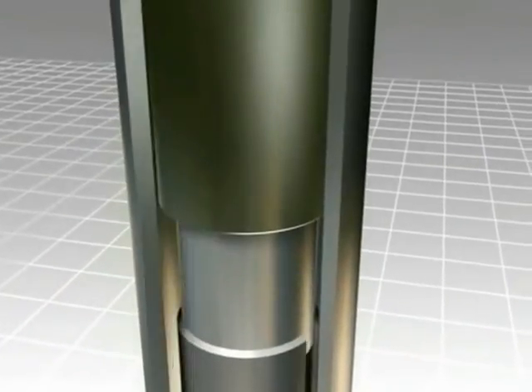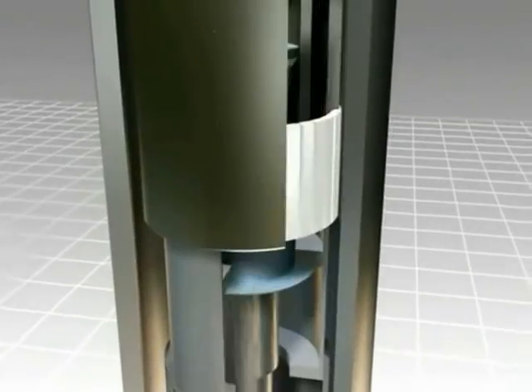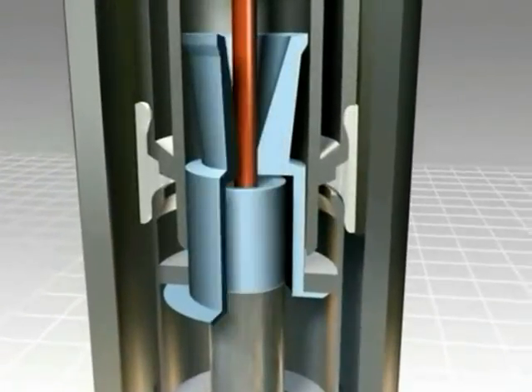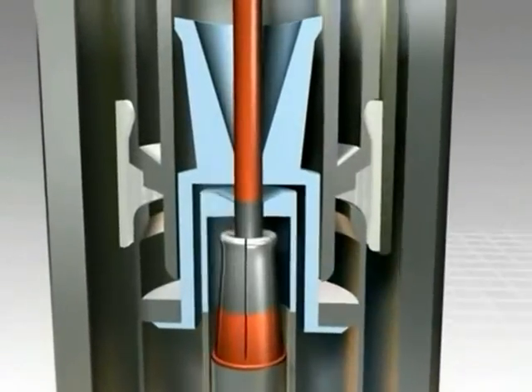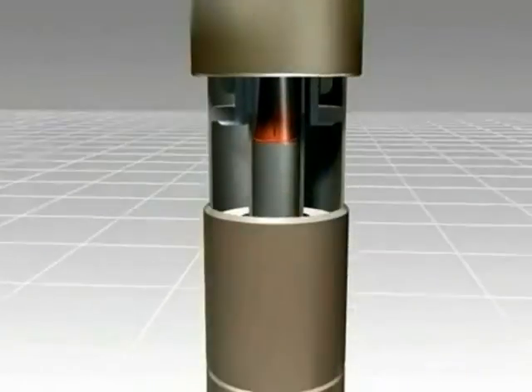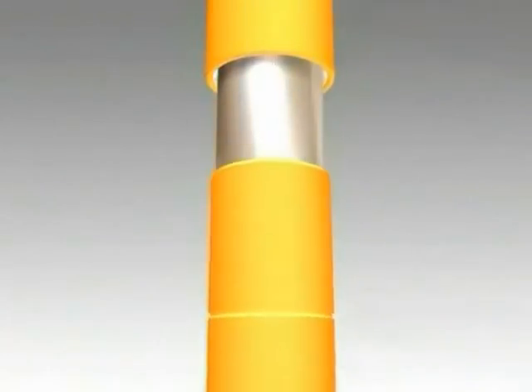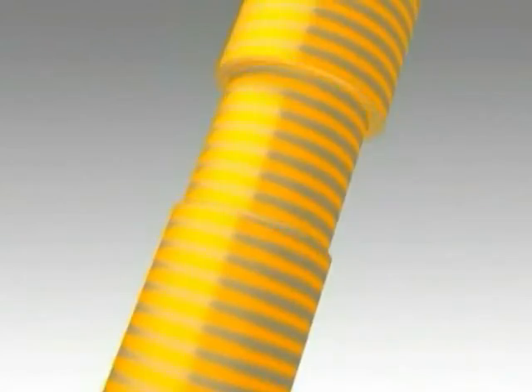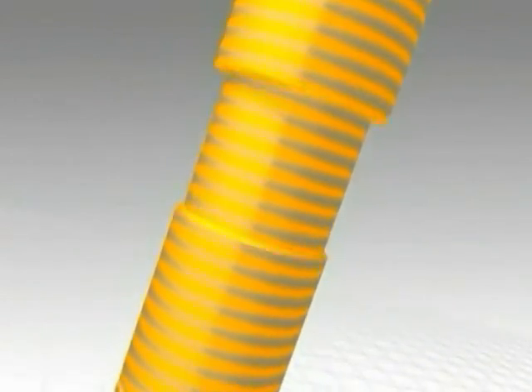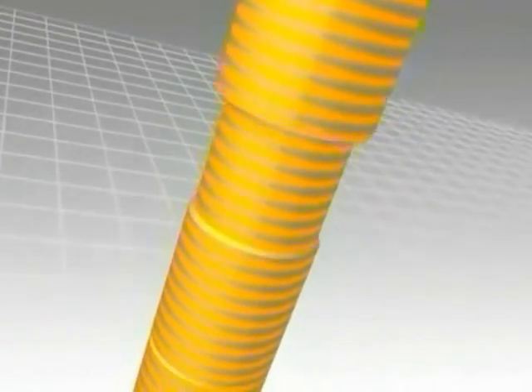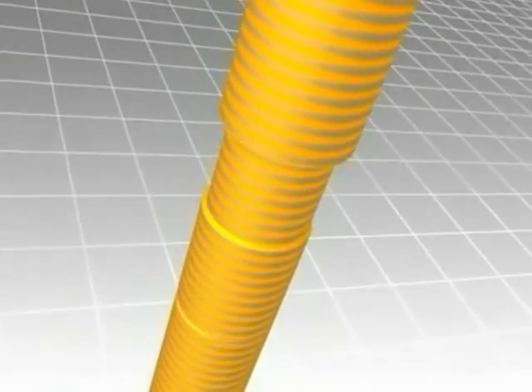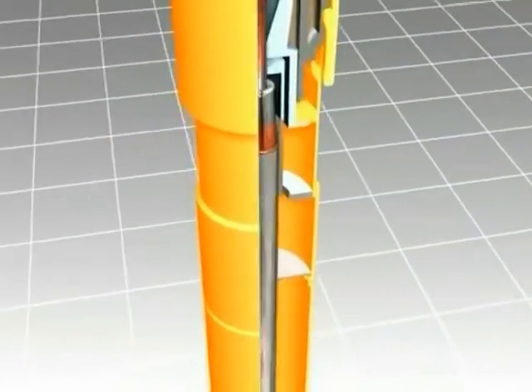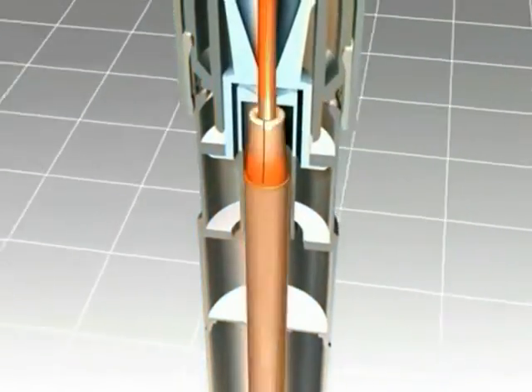At the core of the gas-insulated switchgear is the interrupter unit, which is housed in the circuit breaker module. It operates on a modern self-compression principle. The current path consists of a base, a movable contact cylinder, and a contact carrier. In closed position, the operating current flows through the main contact and through the contact cylinder.